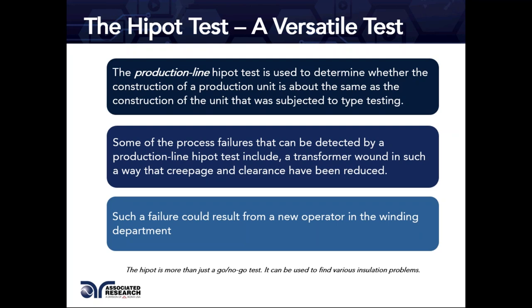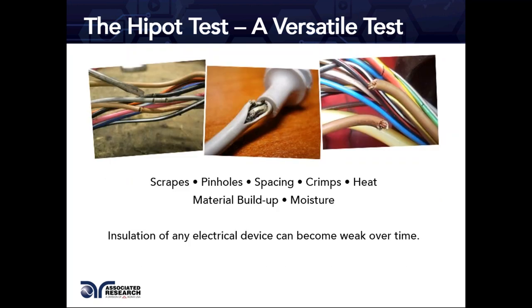The Hypot test in a production environment is more of a go/no-go test with shorter test times. Looking at test standards, the requirements for a type Hypot test versus a production line Hypot test differ — design tests are longer in duration, whereas production line tests may be shorter. The Hypot test is referred to as a versatile test because it detects both quality defects and safety issues.